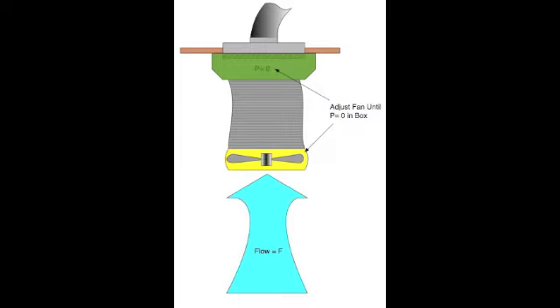If we put a box over the return grill and attach a large fan to that box, we can use that fan to match the air being pulled out of the box by the return grill. When the fan is turned up to the point where the pressure inside the box is zero relative to the room, we know that the air flow into the box is equal to the flow going out of the box. This means that our fan has duplicated the air flow into the return.